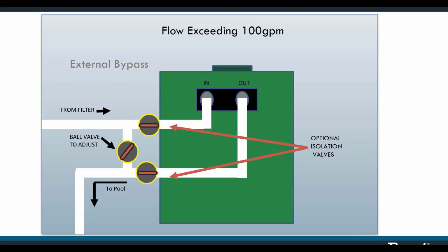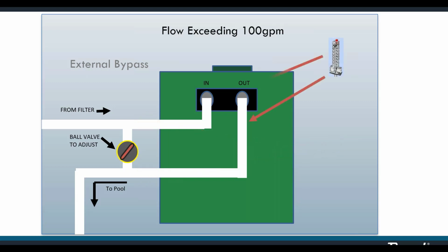Your flow meter should be positioned between the bypass and the heater. Now, putting it elsewhere might only tell you the flow rate on the system and not the flow rate on the heater. So you want to put them here, either coming or going. I like to put them on the inlet side just to make sure I'm not going to have any issues with the heat from the water causing a problem with the flow meter. But again, in this position, you can see it's between the bypass and the heater.